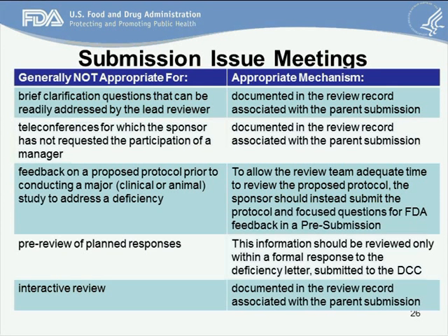Submission issue meetings are not appropriate for pre-review of planned responses. It is our general policy that we don't pre-review your planned responses. This information rather should be reviewed as a formal response to the deficiency letter. So this would be sending in your 510K supplement or your PMA amendment or your IDE amendment with that information.